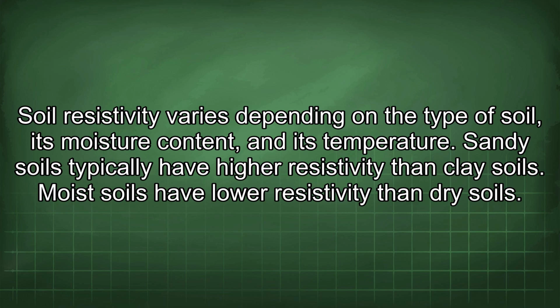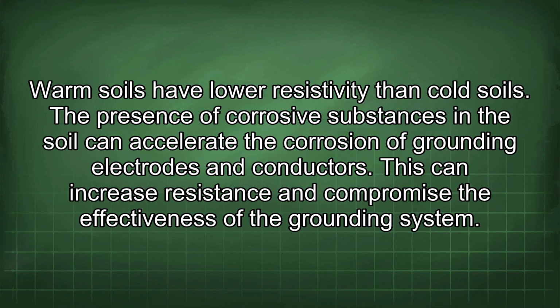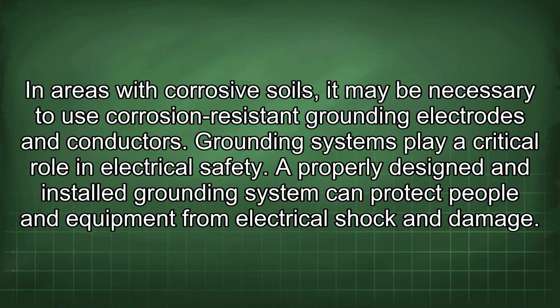Sandy soils typically have higher resistivity than clay soils. Moist soils have lower resistivity than dry soils. Warm soils have lower resistivity than cold soils. The presence of corrosive substances in the soil can accelerate the corrosion of grounding electrodes and conductors. This can increase resistance and compromise the effectiveness of the grounding system. In areas with corrosive soils, it may be necessary to use corrosion-resistant grounding electrodes and conductors.